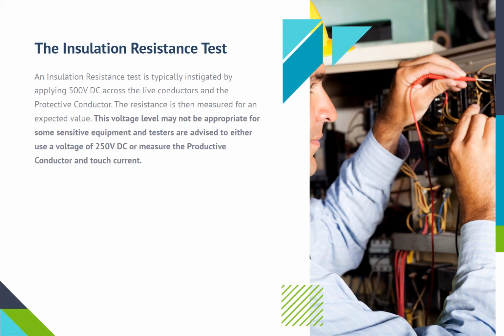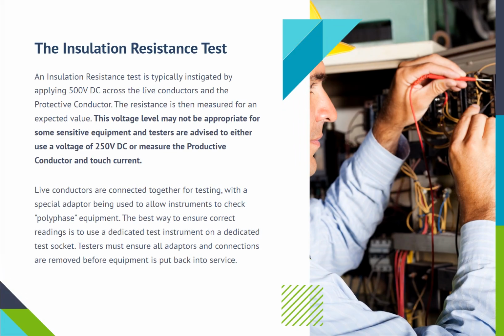An insulation resistance test is typically instigated by applying 500 volt DC across the live conductors and the protective conductor. The resistance is then measured for an expected value. This voltage level may not be appropriate for some sensitive equipment, and testers are advised to either use a voltage of 250 volt DC or measure the protective conductor and touch current.